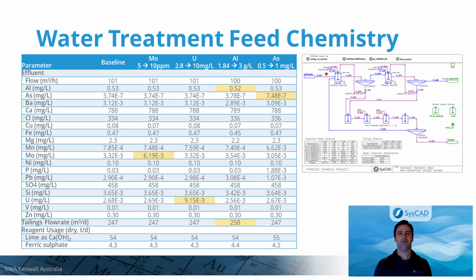Here, the effect of changes in water treatment feed chemistry is predicted. In all cases, results are as expected, with increases in effluent concentration corresponding to increases in the water treatment feed. Because aluminum is a major ion in the raffinate, changing its concentration in the feed affects the tailings volume due to increased formation of aluminum precipitates.